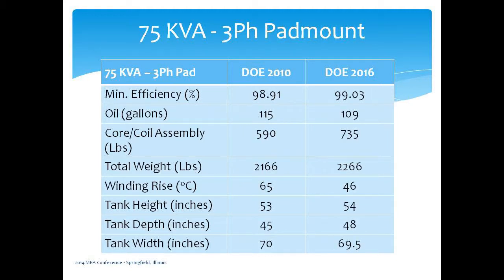I flipped over to the three-phase pad just to give you a feel for a few of those dimensions. When you look at a three-phase pad in particular, because of these slight increases, you're seeing a fairly significant increase in the size and weight of the unit. Notice again the winding rise - the current design was running at 65, and re-optimized to the 2016 design it's running 46 degrees C, which means you've got a little room to overload it. So you've basically got a V8 engine where you used to have a V6, so you get more usable power.